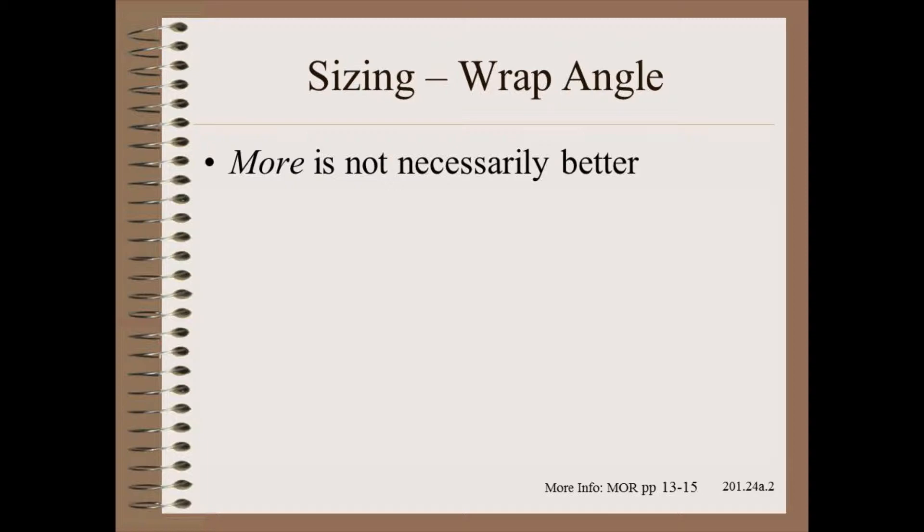One of the most common fallacies of load cell sizing is that more is better with regard to wrap angle. Instead, a better way to view the issue is that you need enough wrap angle. Anything more is fine as long as it didn't cost you much time or money or increase the tendency to wrinkle or cause some other issue. Wrap angle is just one of many tools we have to getting sufficient measurement resolution.